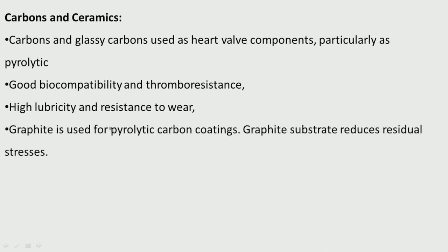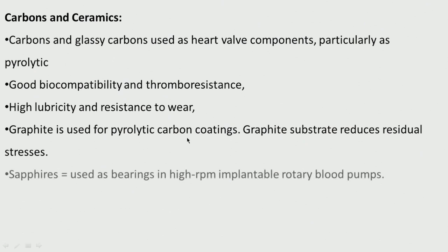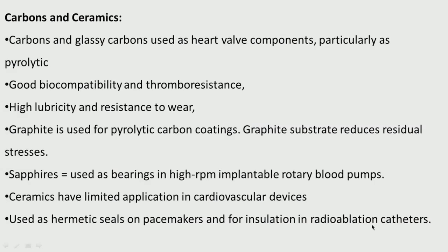Carbon and ceramics: glassy carbon is used in heart valve components. Pyrolytic carbon has good biocompatibility and thromboresistance, high lubricity and resistance to wear. Graphite is used with pyrolytic carbon coatings. Sapphire is used as bearings in high-RPM implanted rotary blood pumps for patients whose heart is too weak to pump adequately.